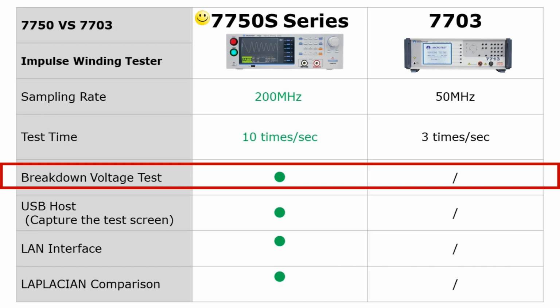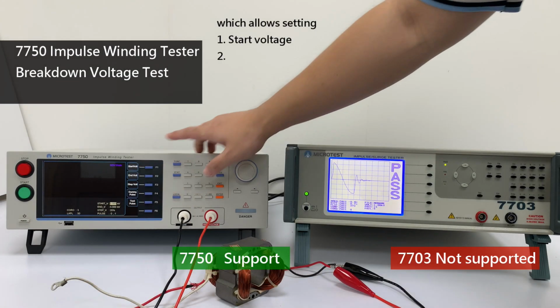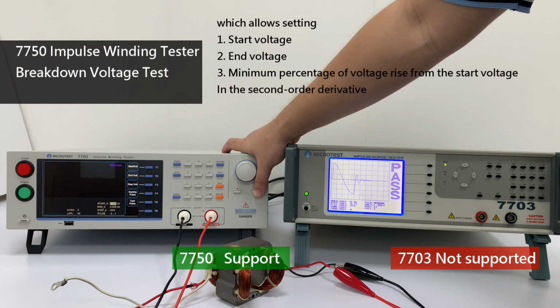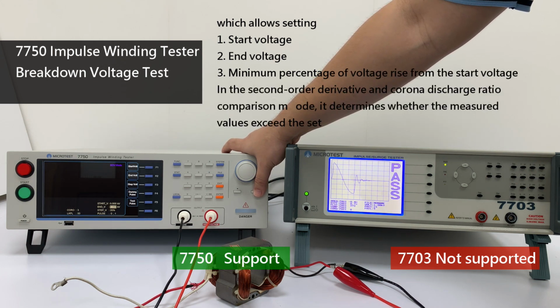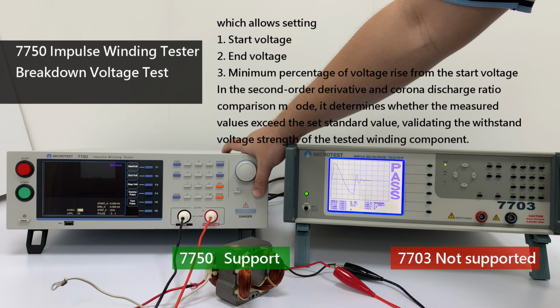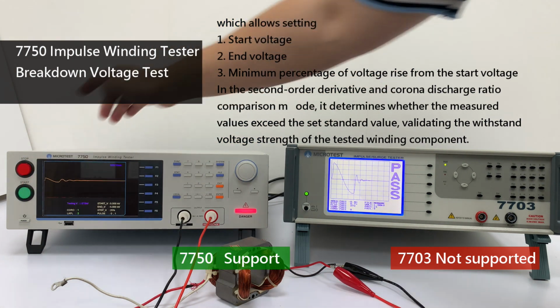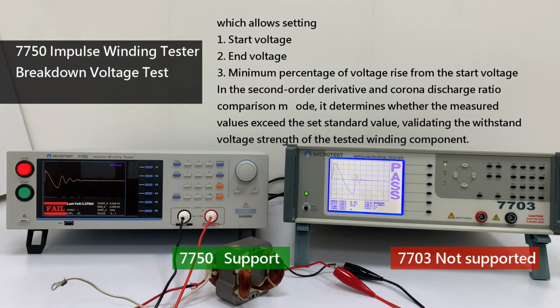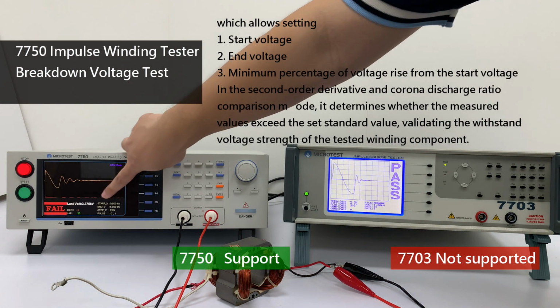It rigorously monitors breakdown voltage testing to ensure insulation performance, which allows setting the start voltage, end voltage and minimum percentage of voltage rise from the start voltage. In the Laplacian comparison mode, it determines whether the measured values exceed the set standard value, validating the withstand voltage strength of the tested winding component.